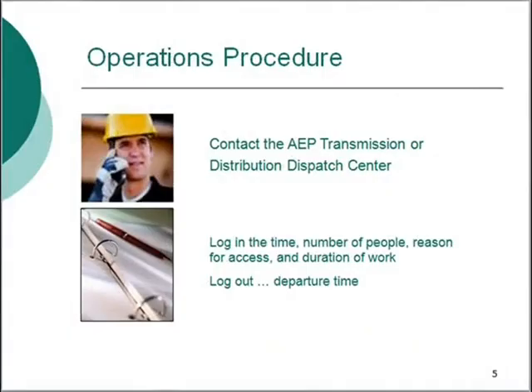When you arrive at a substation, contact the appropriate AEP transmission or distribution dispatch center. The system dispatcher will record your name, number of people in the group, date and time of entry, a brief explanation of the reason for access, and the expected duration of the work. When you are ready to leave, call the dispatcher again to log out of the station. Dispatch telephone numbers are available from your AEP point of contact.